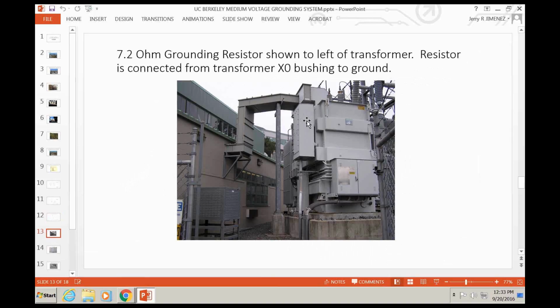However, there is an X0 bushing in this box, and its connection goes down through a conduit, goes underground, and comes up into this grounding resistor. Of course, the insulation on that cable needs to be good for at least 7,200 volts, but I'm pretty sure it's 15 kV cable. The reason is that when you get a ground fault, all of a sudden that X0 bushing rises above ground to, I think, 7,200 or possibly 12.47 kV. Let me think about it a little more before I give a number. But anyway, the cable has to be insulated for full phase voltage.